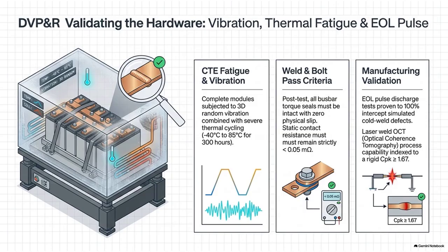Exactly. Standard 2-wire multimeters are useless here. They utilize a 4-wire Kelvin resistance measurement technique. How does that work? It uses 2 wires to inject a highly precise, known test current across the joint and a separate, dedicated set of 2 wires to measure the voltage drop directly at the connection points. This entirely eliminates the resistance of the test leads and the contact resistance of the probes themselves, isolating the true absolute resistance of the weld or bolted joint.